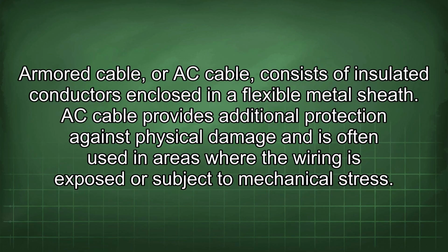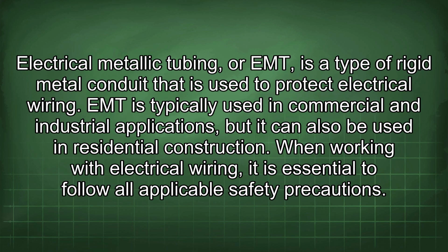Armored cable, or AC cable, consists of insulated conductors enclosed in a flexible metal sheath. AC cable provides additional protection against physical damage and is often used in areas where the wiring is exposed or subject to mechanical stress. Electrical metallic tubing, or EMT, is a type of rigid metal conduit that is used to protect electrical wiring. EMT is typically used in commercial and industrial applications, but it can also be used in residential construction.